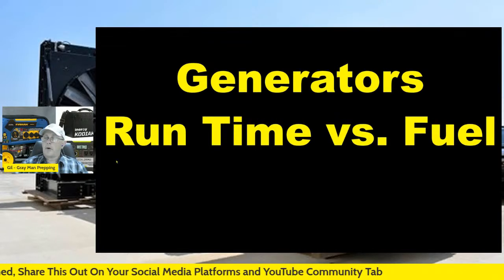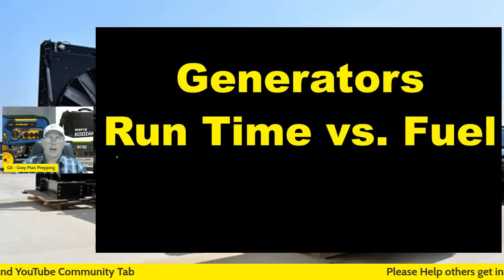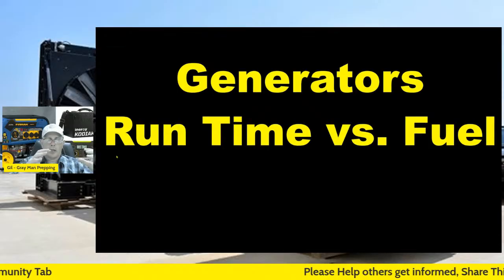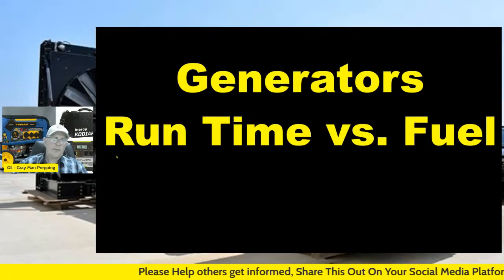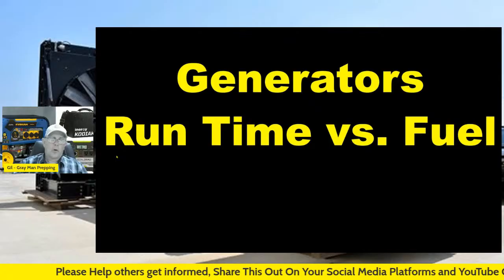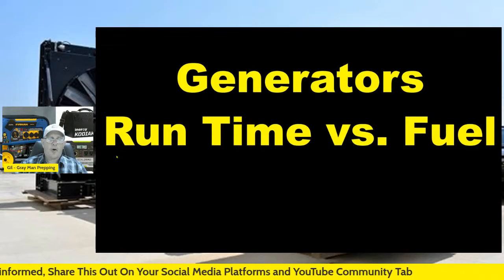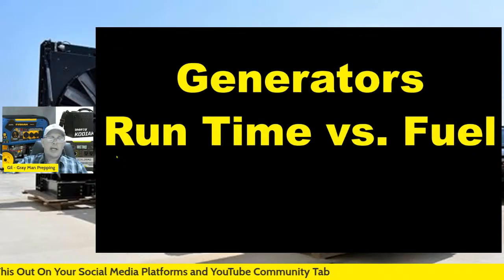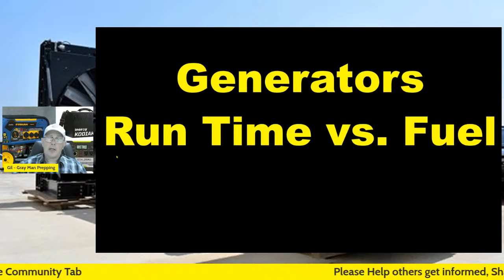Now, the construction company I work for, Mountain Cascade, we did a workaround on that. We built an oil reservoir onto the generator. So instead of taking a quart or a quart and a half of oil, it took a gallon and a half of oil, and it circulated the oil through it. So it was getting serviced all the time. So we only had to service it every 250 hours.